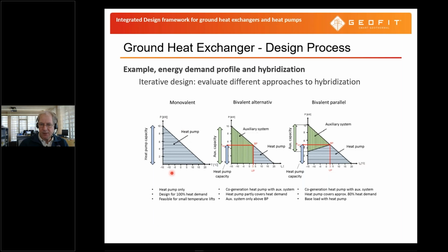What we can see here is that, for instance, we can decide to do everything with a heat pump. Another possibility is to do part with the heat pump, and then once we exceed a certain capacity, we switch over completely to the auxiliary system. This we would do, for instance, if also we want to increase the temperature in the auxiliary system from a low temperature to a higher temperature to achieve a higher capacity in the emission system. And we can also do it in a different way that I hope Michael will explain a bit later.